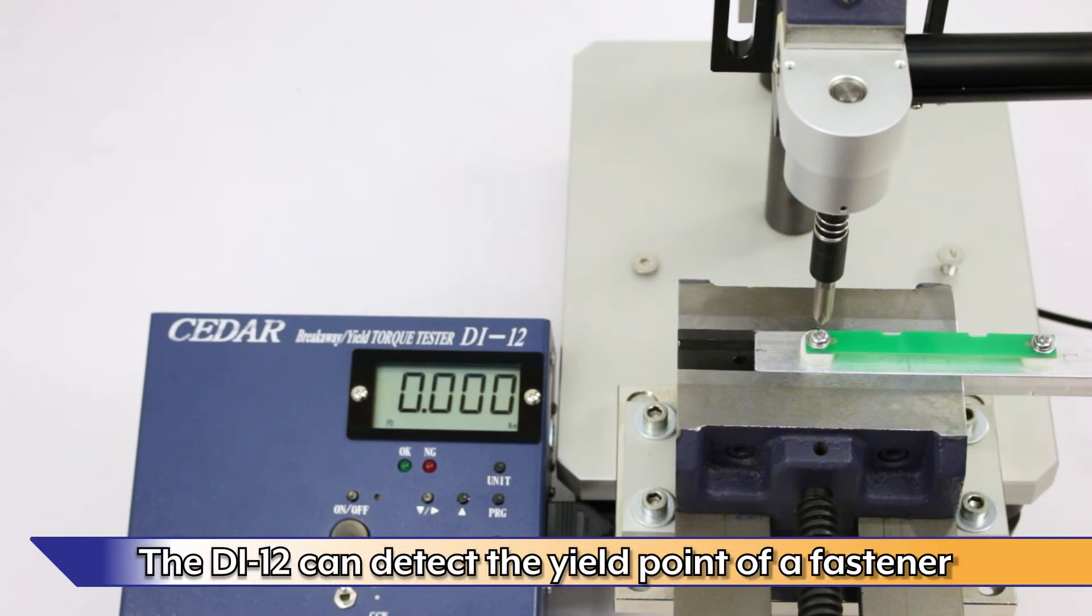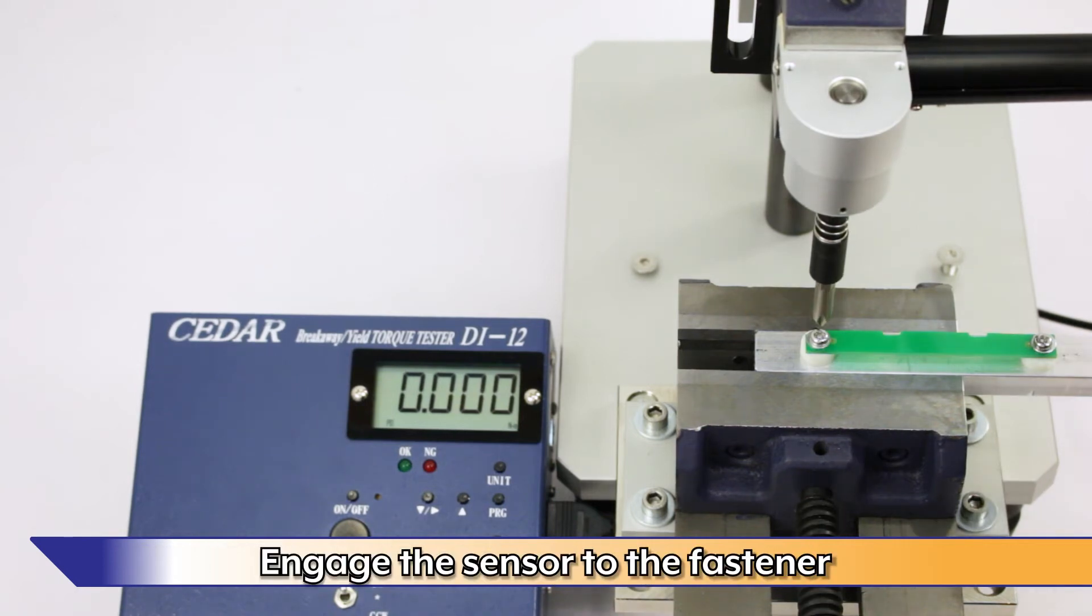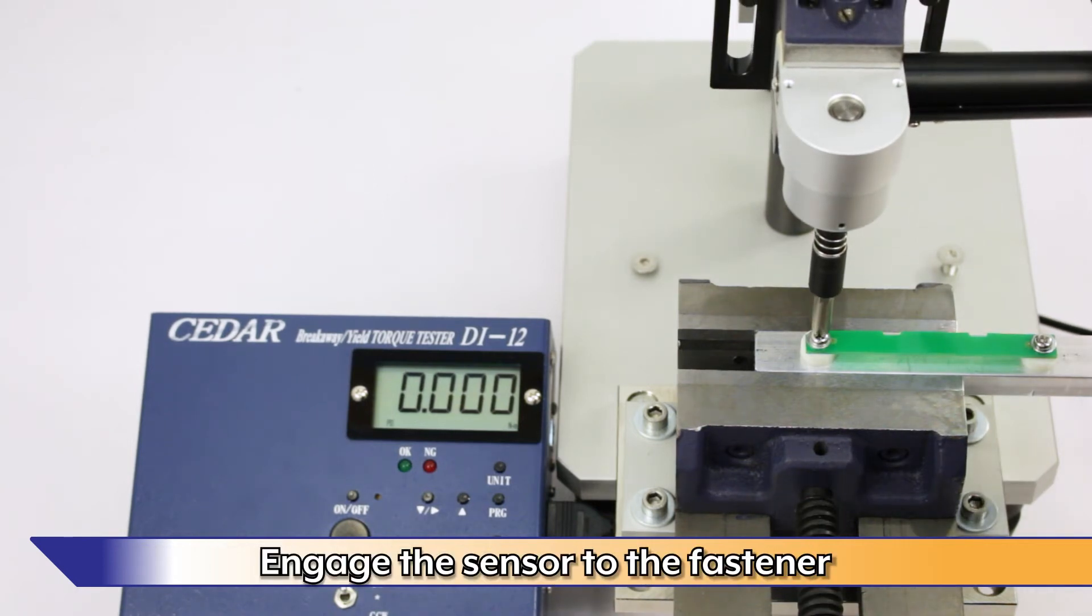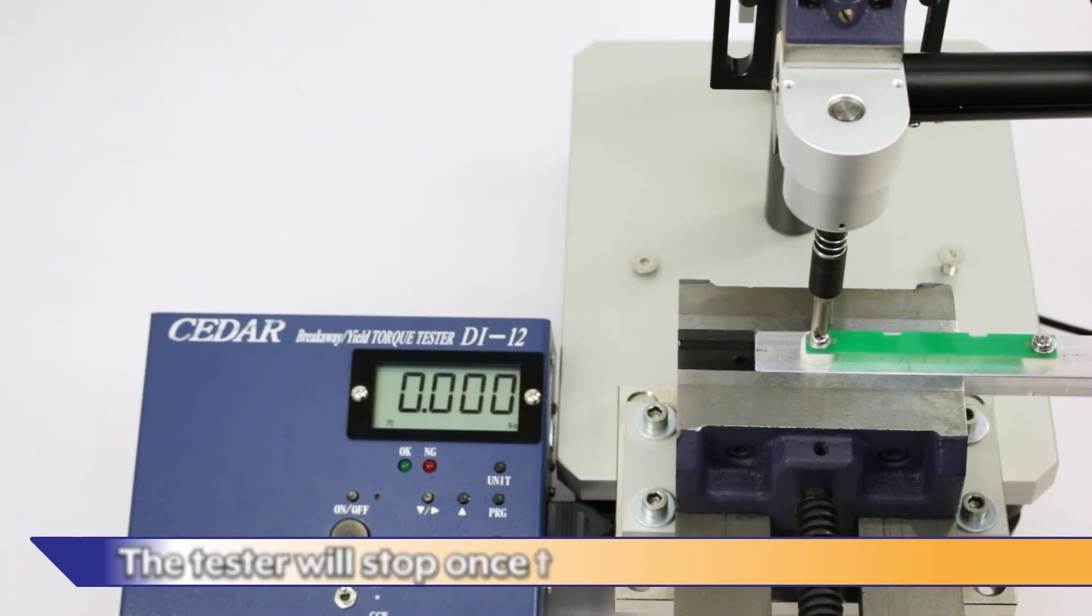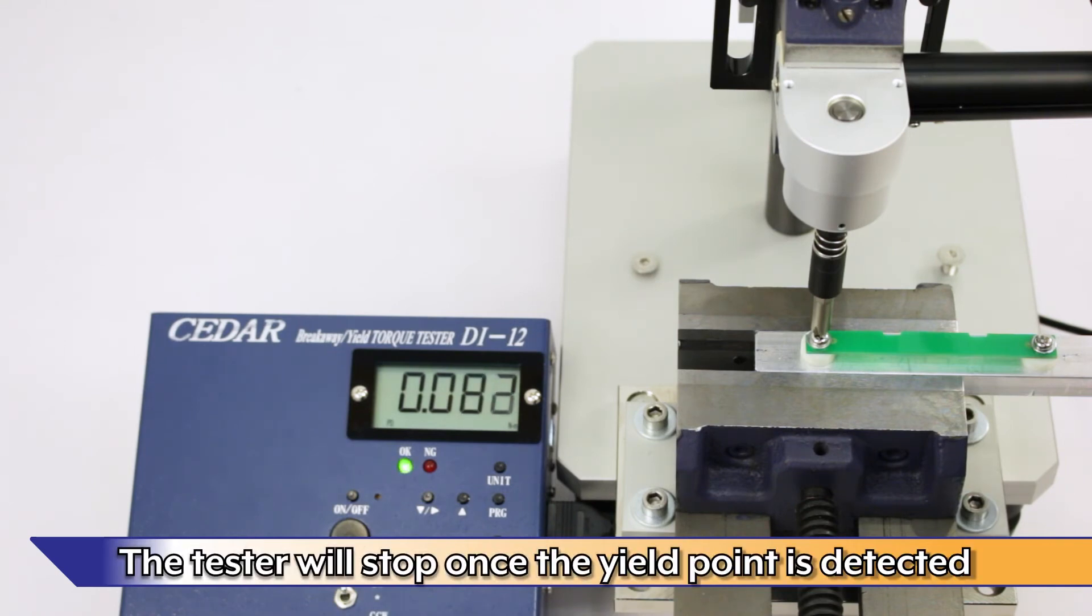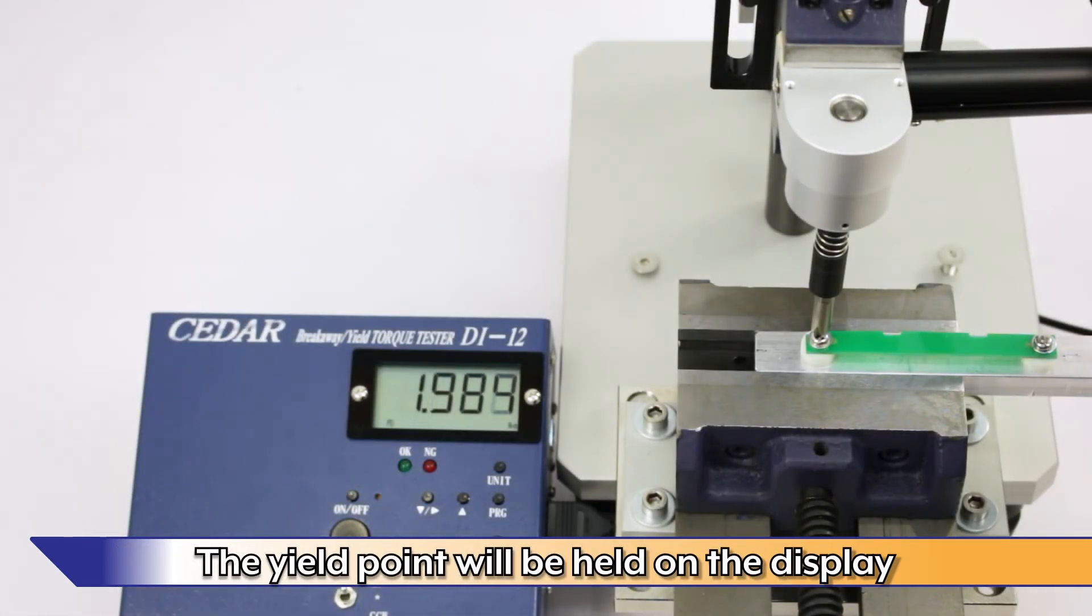The DI-12 can automatically detect the yield point of a fastener. Engage the sensor to the fastener. Press the Start-Stop button to begin the test. The tester will stop once the yield point is detected. The yield point will be held on the display.